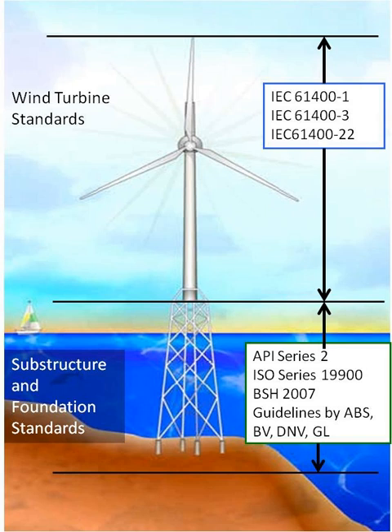Turbulence intensity quantifies how much the wind varies, typically within 10 minutes. Because the fatigue loads of a number of major components in a wind turbine are mainly caused by turbulence, the knowledge of how turbulent a site is of crucial importance. Normally the wind speed increases with increasing height — in flat terrain logarithmically, while in complex terrain the wind profile is not a simple increase and separation of flow might occur, leading to heavily increased turbulence. The extreme wind speeds are based on the three-second average wind speed, and turbulence is measured at 15 m/s wind speed as defined in IEC 61400-1 edition 2. For US waters, several hurricanes have already exceeded wind class IA with speeds above 70 m/s, and efforts are being made to provide suitable standards.